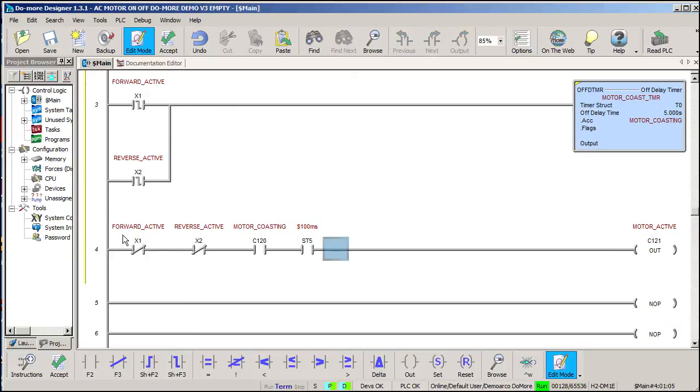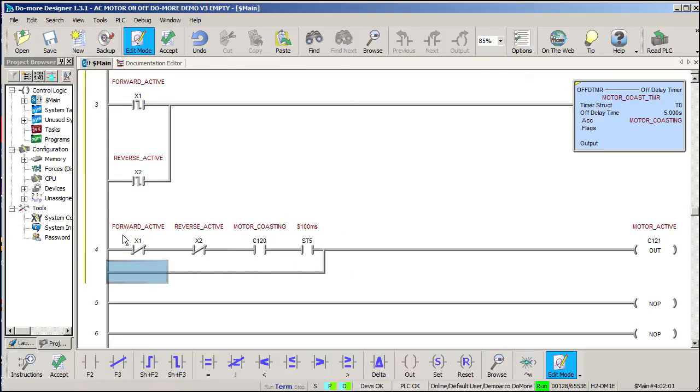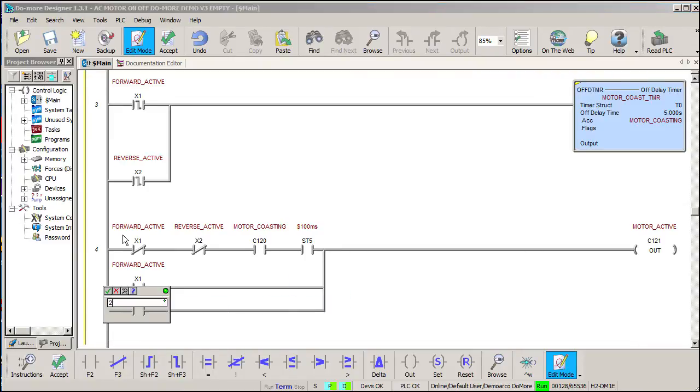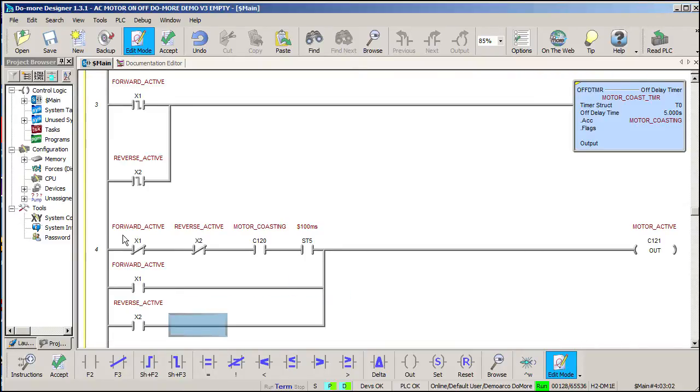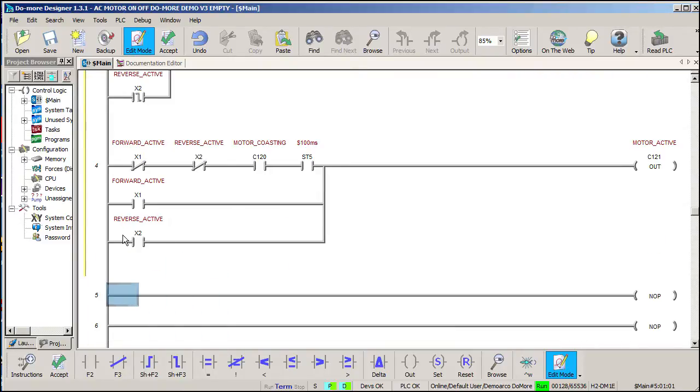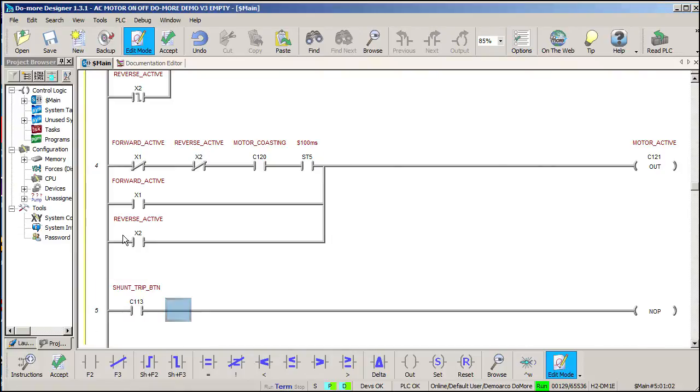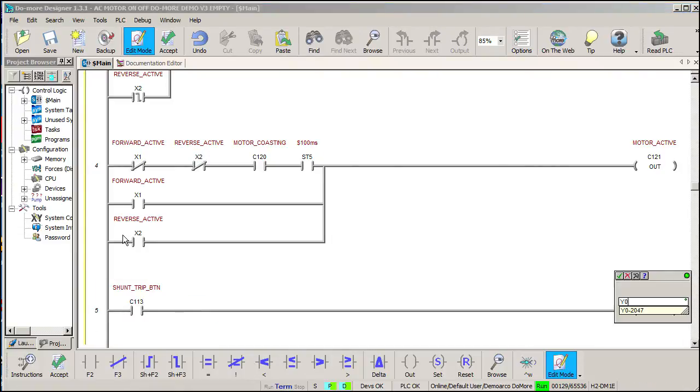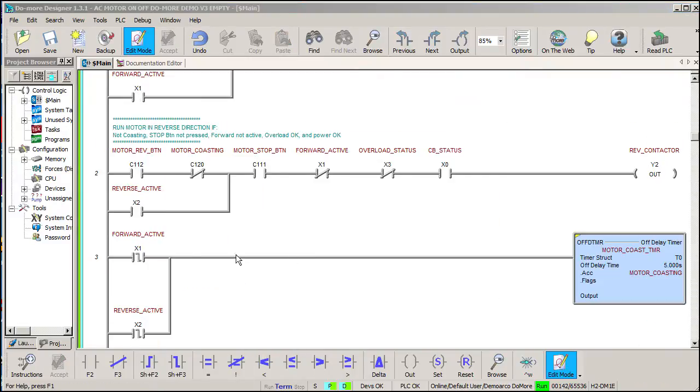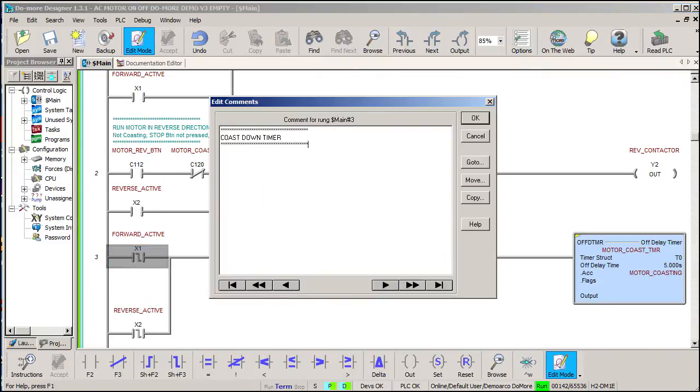This will drive the stop button indicator which is just the inverted version of this motor active bit. We also want to turn on the motor active bit if either contactor is active. Again, this will turn off the stop button indicator. Finally, we need for the circuit breaker shunt trip button to trip the breaker which is at Y0. And let's add some comments for all these rungs.